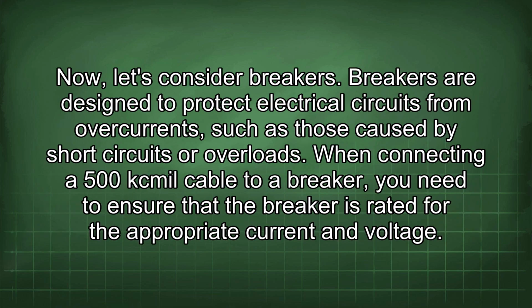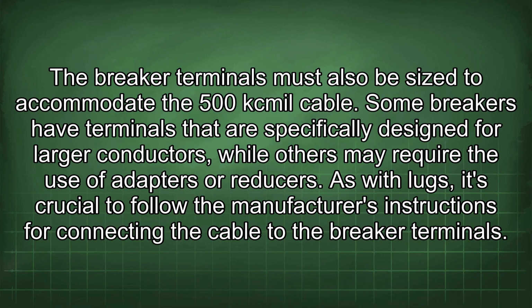Now, let's consider breakers. Breakers are designed to protect electrical circuits from overcurrents, such as those caused by short circuits or overloads. When connecting a 500 kcmil cable to a breaker, you need to ensure that the breaker is rated for the appropriate current and voltage. The breaker terminals must also be sized to accommodate the 500 kcmil cable.